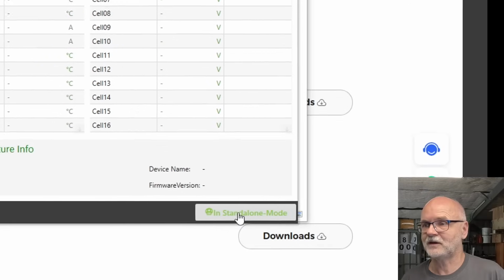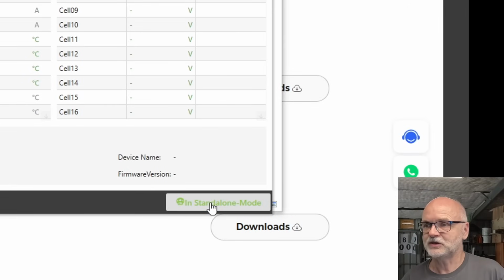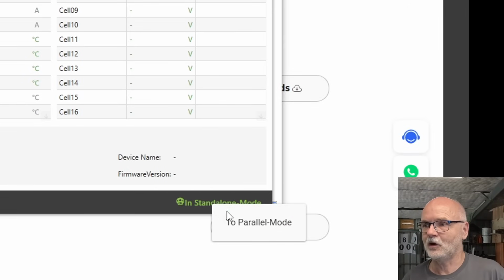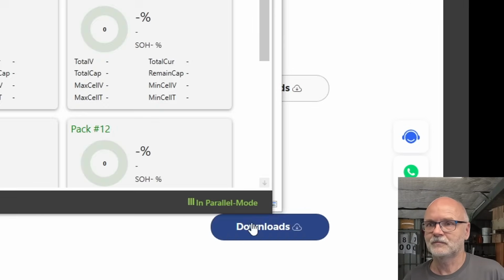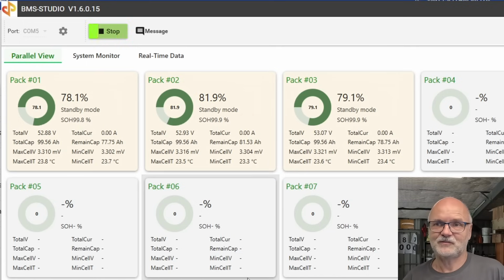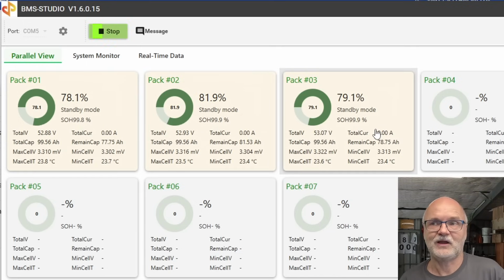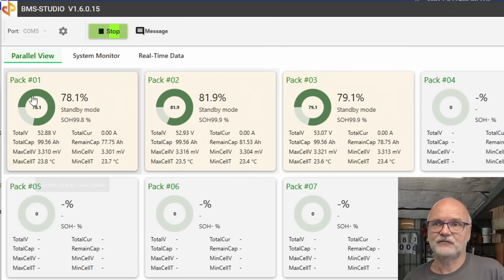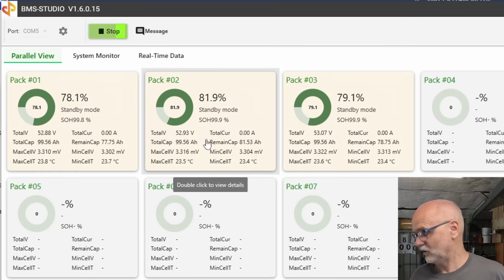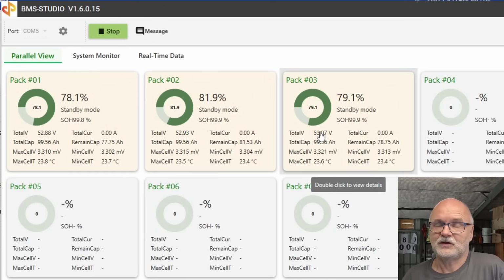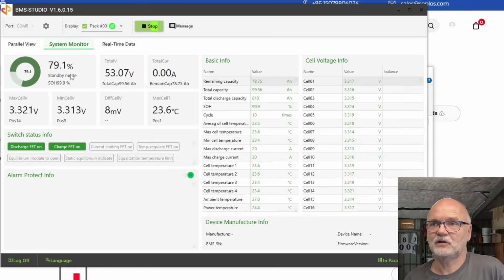So we have to click on this button in the bottom right-hand corner and change the software from standalone to parallel mode. This automatically connects back to your master battery, which reads all the information of the slave batteries as well. You can see they have got different states of charge and different voltages, because all the circuit breakers are still off. You can also click on any of the BMSs, and it gives you an overview of all the electrical values.